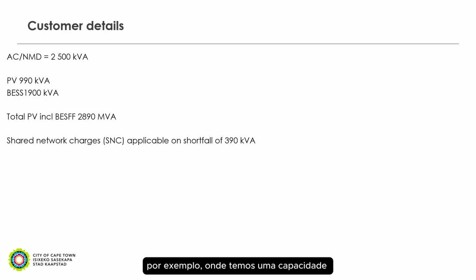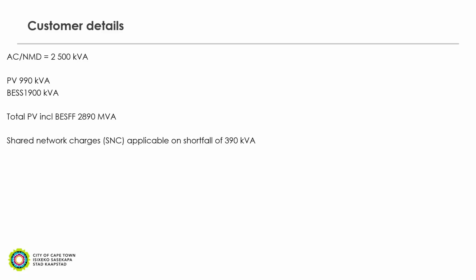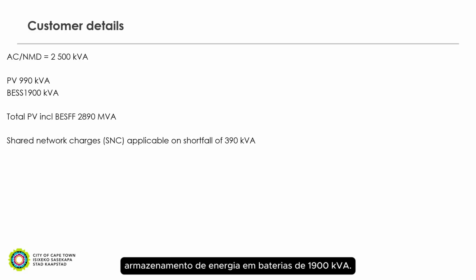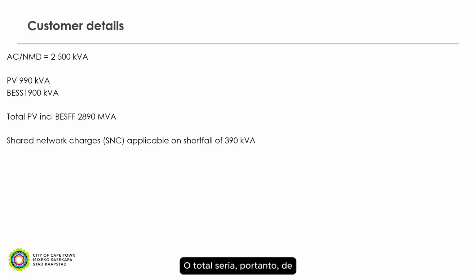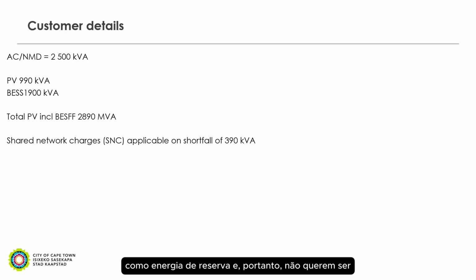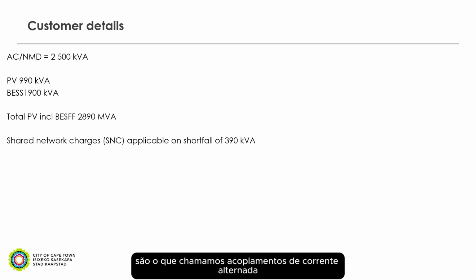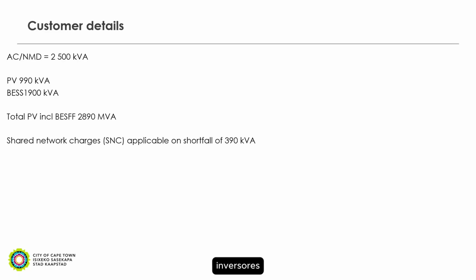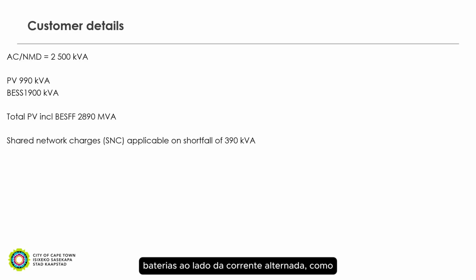So, a specific case, for example: we have an authorized capacity, also known as the notified maximum demand, of 2500 kVA. The customer has an existing PV of 990 kVA installed, and then wants to add a battery energy storage system of 1900 kVA. Therefore, the total would be 2890 kVA. So here we have some challenges, where the customers deem the battery systems as backup and therefore do not want them to be added to the PV system, but these are what we refer to as AC coupled systems, and they are using battery inverters to connect the batteries to the AC side as backup.